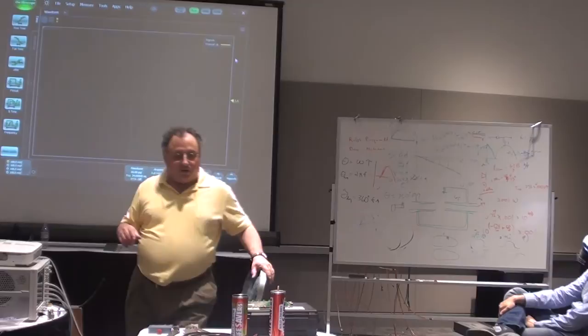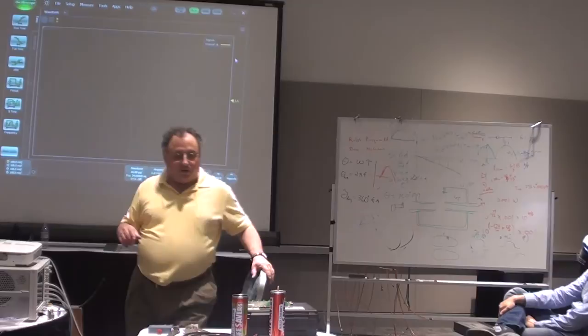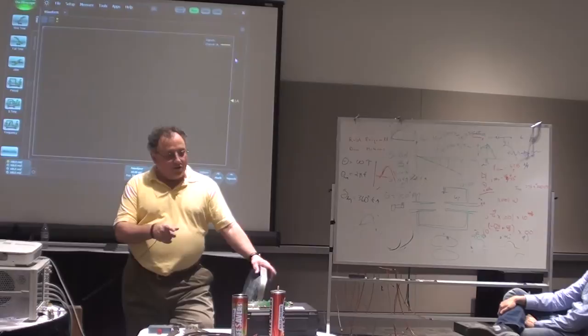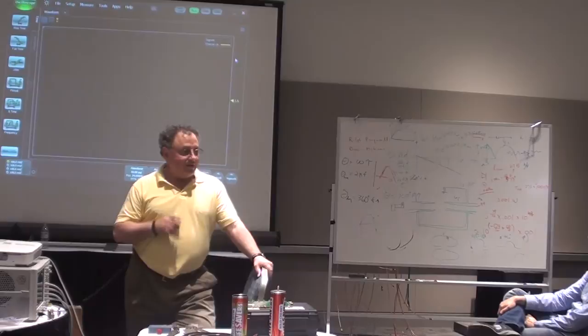We are not going to use it in the super fancy mode, all four channels initially. We're just going to use it as a simple one channel time domain reflectometer. I did learn how to use the AutoCal kit, but that again is for the advanced. You've got nothing better to do by the end of next week, and I can show you how to play with that. It's rather handy. It does have a manual calibration mode, which I'll walk you through right now.